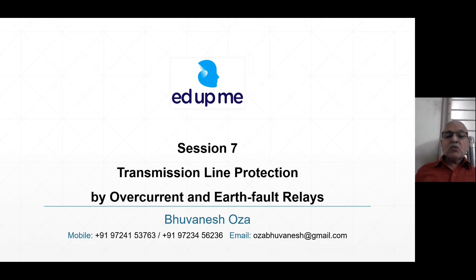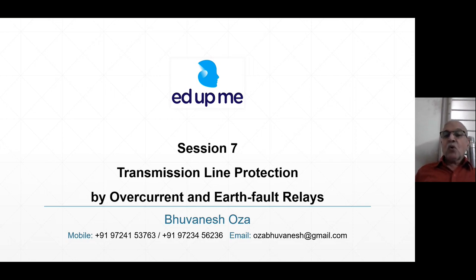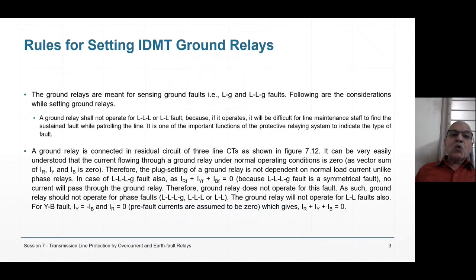Today we are going to see the ground relay — how ground relays are set. That is for LG and LLG faults. LLG fault is a hybrid fault: LL is a line fault, but LLG is a ground fault. Because the ground relay is more sensitive, it will operate first in LLG faults. So we consider LLG and LG, and LG fault current — R-to-G, Y-to-G, or B-to-G — is what we consider for relay calculations.